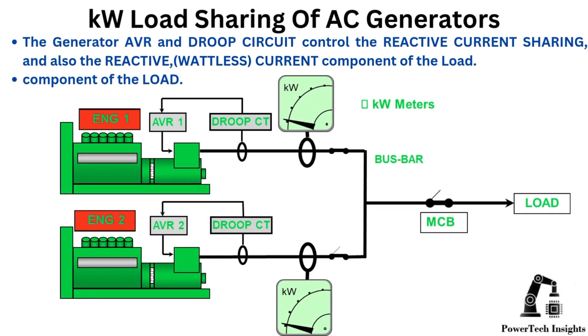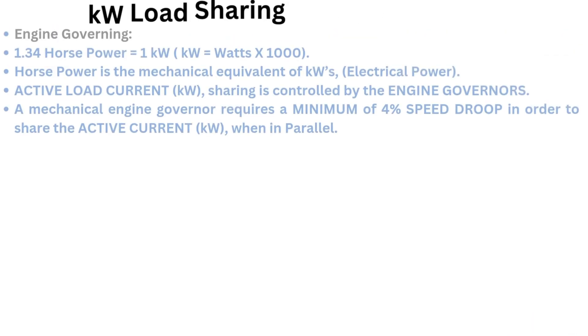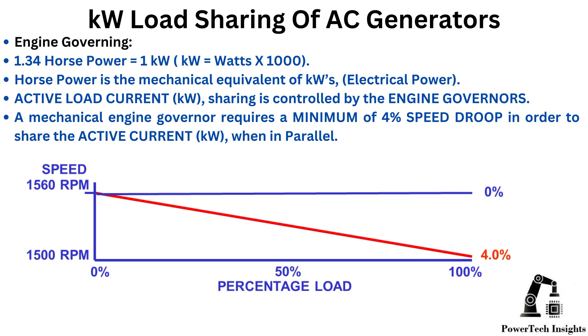KW load sharing of AC generators. The generator AVR and droop circuit control the reactive current sharing and the reactive (wattless) current component of the load. The diesel engines must have similar no-load to full-load governor characteristics to share the active current (power factor 1), or kW component of the system. Engine governing: 1.34 horsepower equals 1 kilowatt; horsepower is the mechanical equivalent of kW electrical power. Active load current (kW) sharing is controlled by the engine governors. A mechanical engine governor requires a minimum of 4% speed droop in order to share the active current (kW) when in parallel.